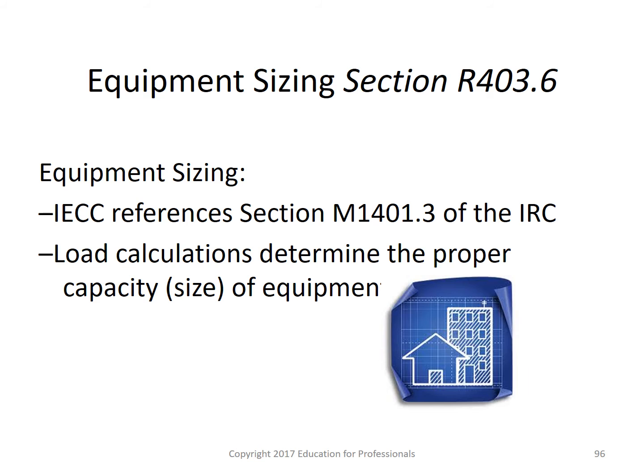And here's a bit on the importance of equipment sizing. The reason for these load calculations and the second item, where the goal is big enough to ensure comfort but no bigger, all revolve around that one of the most important decisions regarding a new building is the type of heating, ventilation, and air conditioning system to install. Equally critical is the heating and cooling contractor selected. The operating efficiency of a system relies on proper installation to achieve the performance rating.